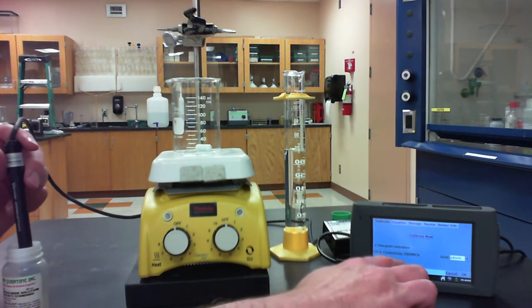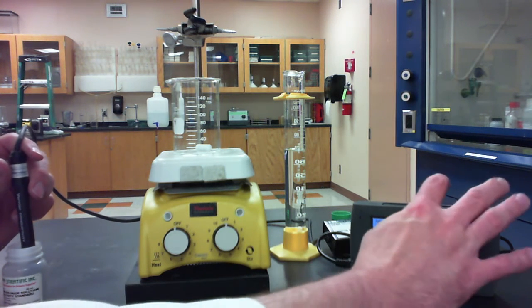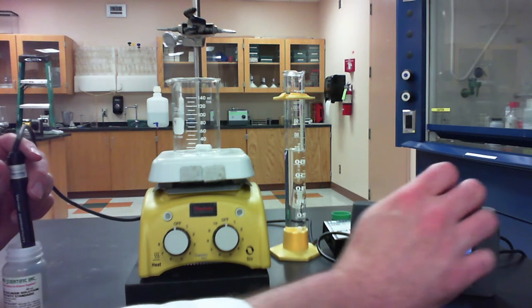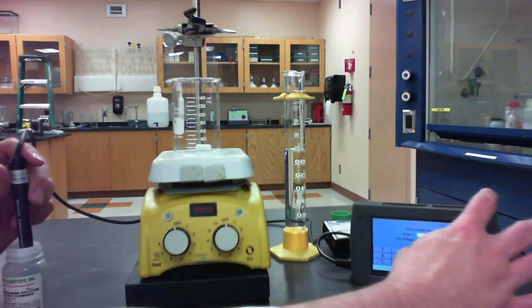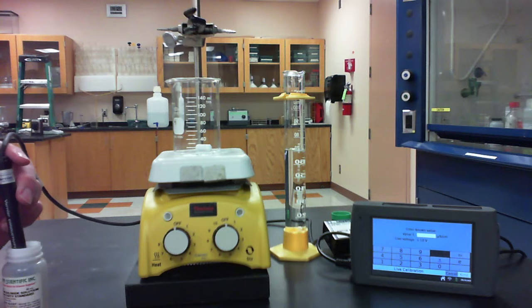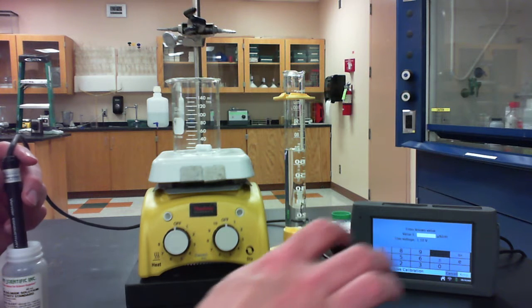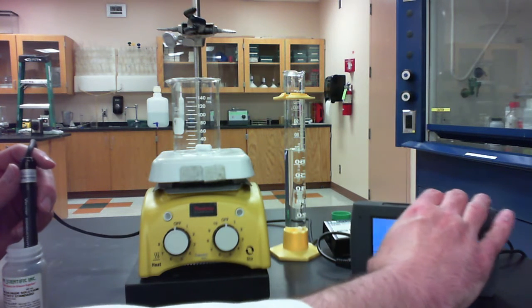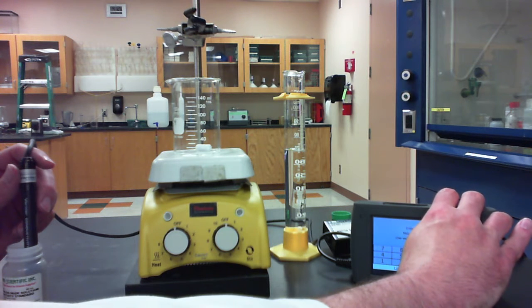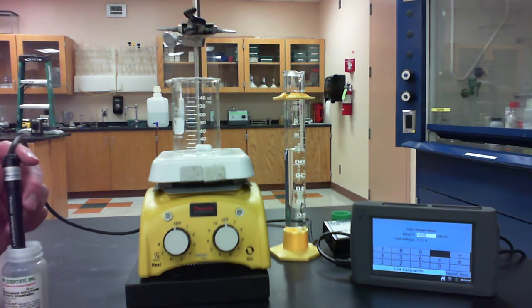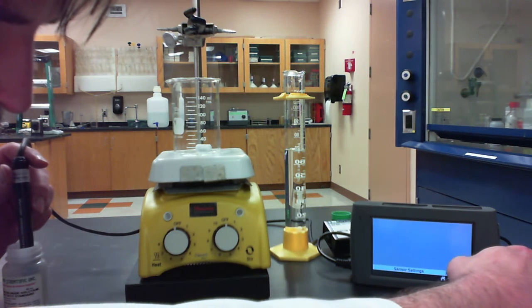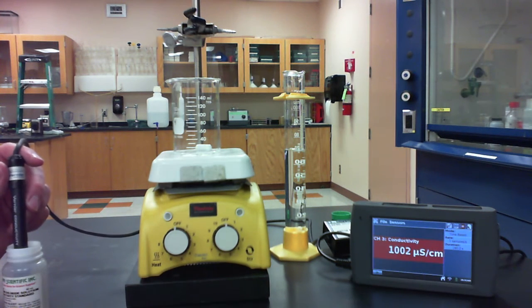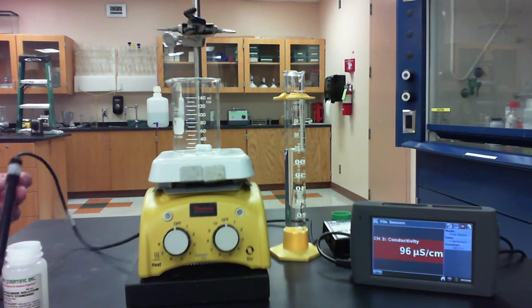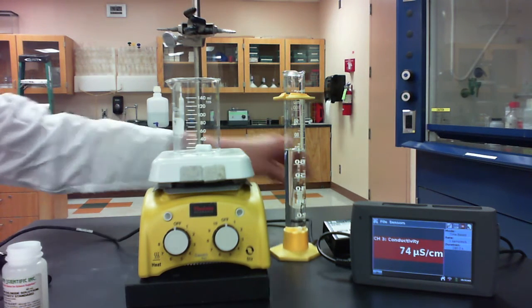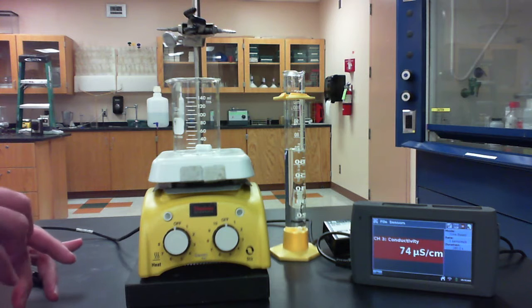Once it's hooked up to the LabQuest, I'll click on the unit bar where we see the units of conductivity. I will then press the calibrate button and a 1-point calibration. Make sure that the conductivity probe has been thoroughly rinsed and dried, and then place it inside of the calibration solution and set the calibration to 1000 microsiemens per centimeter. Microsiemens are units of conductivity.